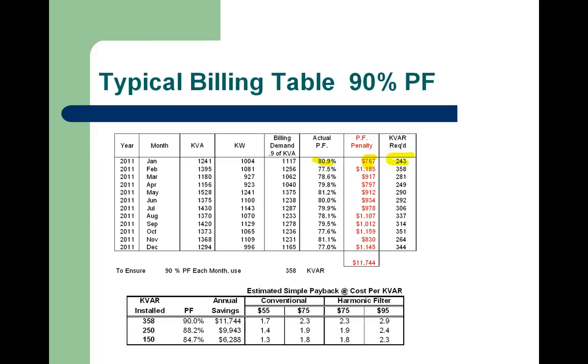range of dollars. You find here, if we installed a full 358 kVAR, and I'm going to use my highlighter for a moment, there would be annual savings of over $11,000. And we have a couple of different paybacks here. So for instance, if we required a harmonic filter and there were some existing disconnects that we could use, we may be able to get into this area here.